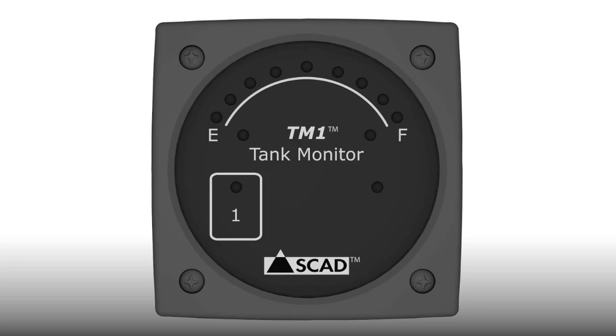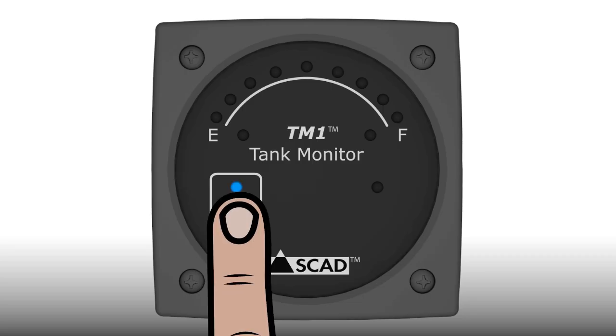When power is applied to the monitor, the lights will cycle through, turning on as it boots up. To enter setup mode, press and hold the touchpad. In a couple seconds, lights will turn on, starting from the 1/8 light through the 7/8 light, and then turn off. This means the monitor is in setup mode.